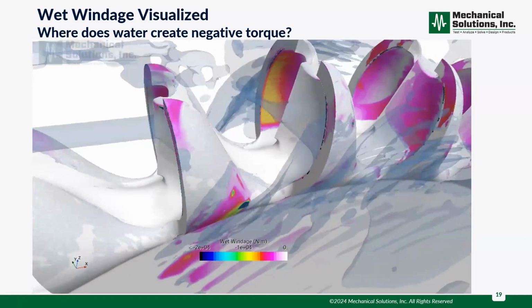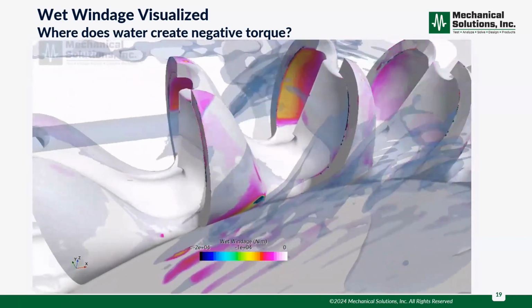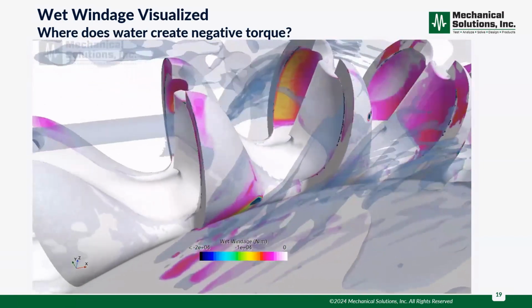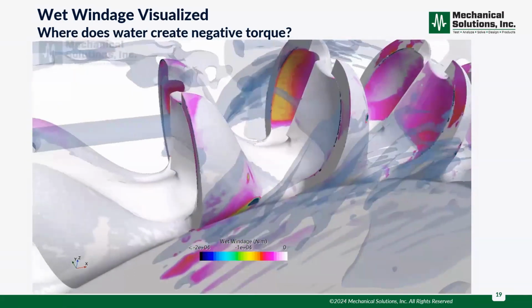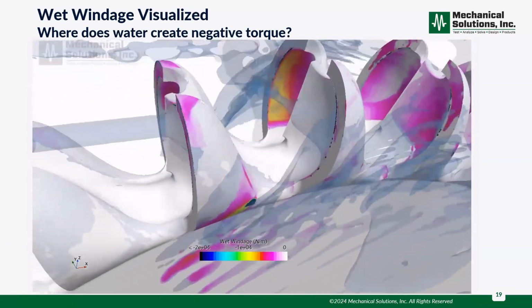You see that flashing up there at the bottom of the backside of the bucket? Those water jets, the water jet is actually coming back. It does a 180 in the bucket and then hits it there, and that creates a negative moment. The wheel is quite fast, so you're hitting water there that really creates a loss.